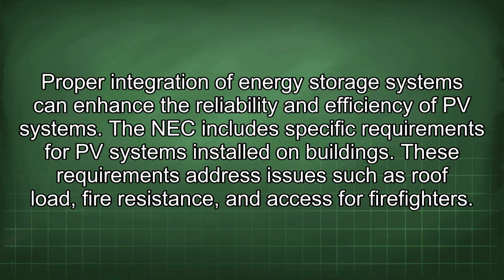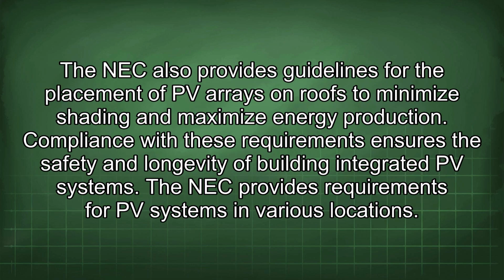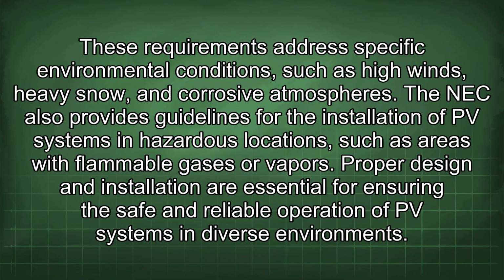The NEC includes specific requirements for PV systems installed on buildings. These requirements address issues such as roof load, fire resistance, and access for firefighters. The NEC also provides guidelines for the placement of PV arrays on roofs to minimize shading and maximize energy production. Compliance with these requirements ensures the safety and longevity of building integrated PV systems. The NEC provides requirements for PV systems in various locations. These requirements address specific environmental conditions such as high winds, heavy snow, and corrosive atmospheres.